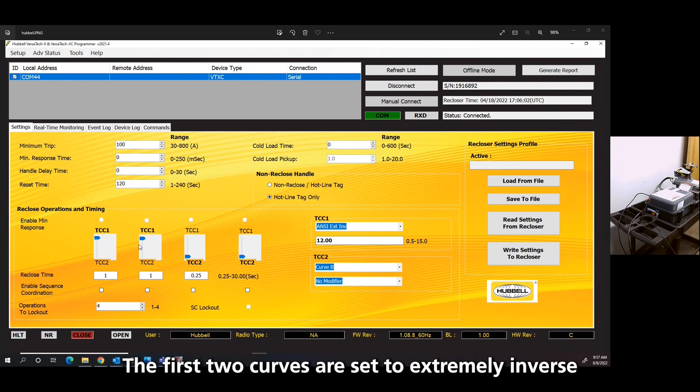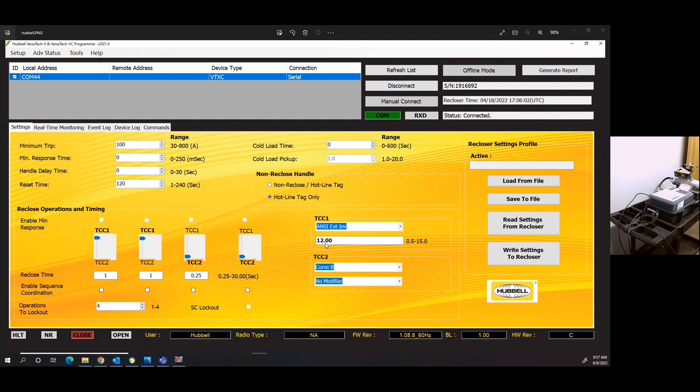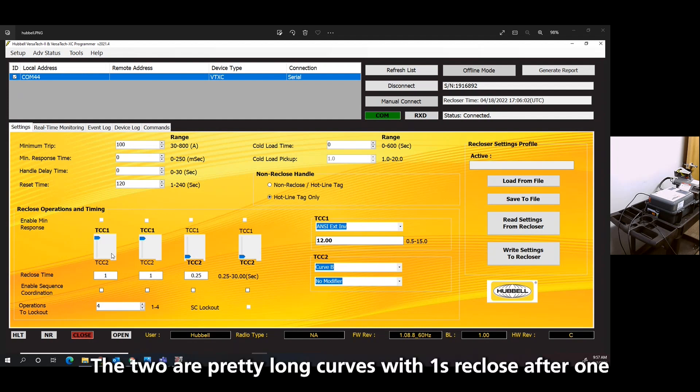The first two curves are very long. They're an ANSI extremely inverse, with the time multiplier 12. So those are two pretty long curves with one second reclosers after them.